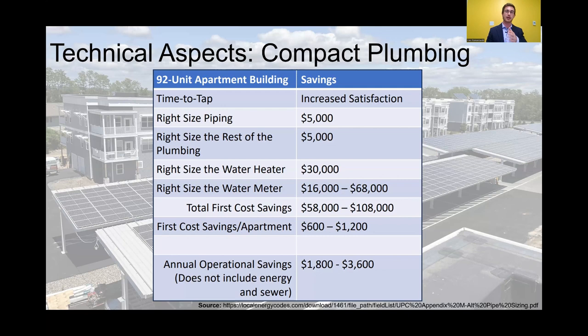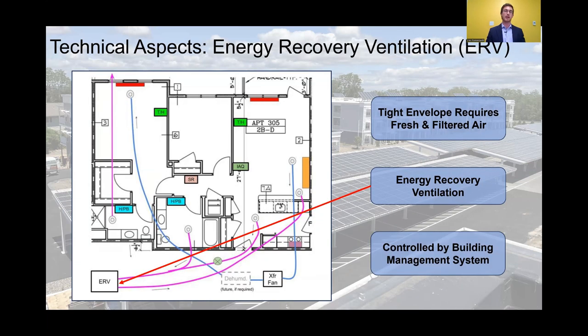And that's going to vary a lot. But your projected first cost savings for the 92-unit apartment building case study that they did was $600 to $1,200. And then your annual operating savings were between $1,800 to $3,600. That's a lot just for right-sizing your pipes. Now let's get back to some of Solara's specs.